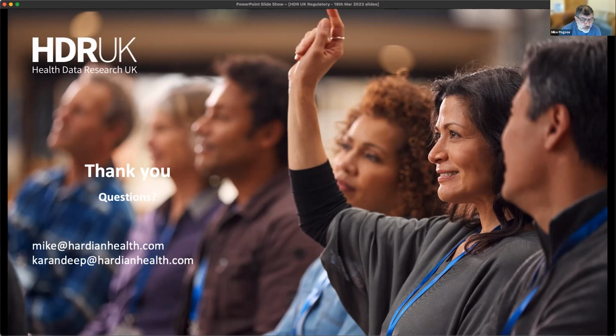So what we often find is that these research databases are limited either in the patient demographic or in the input equipment demographic, like what makes and models of scanners, say, or what types of signal capture and analysis systems have been used. So to answer that, number one, the bigger question is how generalizable are you? Have you thought about the intended use and the intended patient population fully to begin with, which might require you to go to another database?